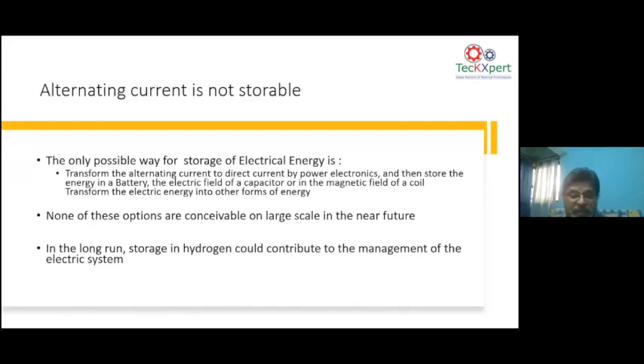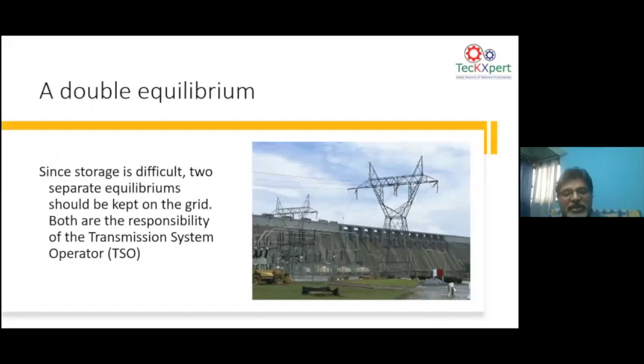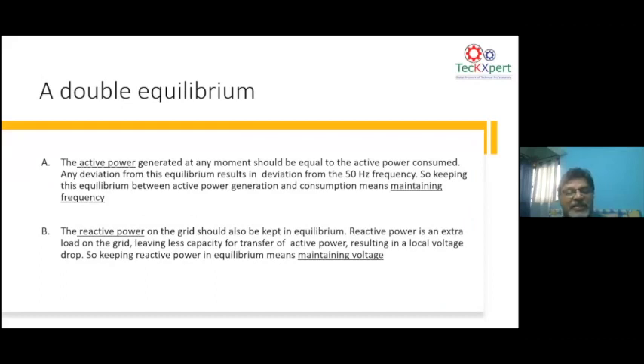Now, in its natural form of control, it's a double equilibrium when it comes to a power system. So when I say double equilibrium, if you look at the next slide, there's an active power equilibrium and there is a reactive power equilibrium. When you say an active power equilibrium, we need to make sure that the active power generated at any moment should be equal to the active power consumed. That means you have to maintain the frequency. That's where the frequency stability comes. If your active power generated and consumed are equal, then your frequency remains at 50 hertz. As it changes, suddenly the frequency varies.